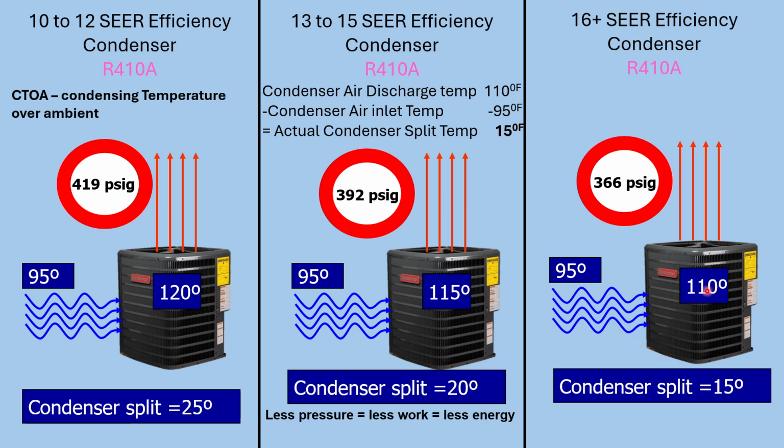It's 110-degree saturation temperature. So that's why I say I would always, depending on what your pressure is, but if you think it's a 20-degree split and it's not, and you're lower, do the calculation again with 15 or even 10 and see where you are. Because, like I say, the condensers of today do not follow the convention. If they can use a lower design temperature differential, they will, and they don't publish that. They just do it.